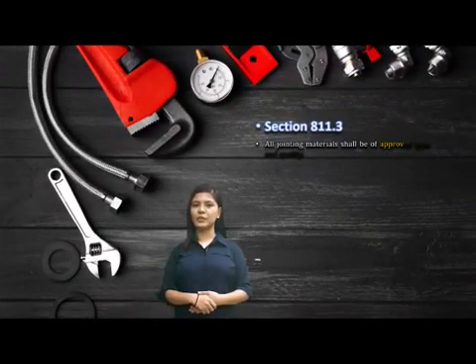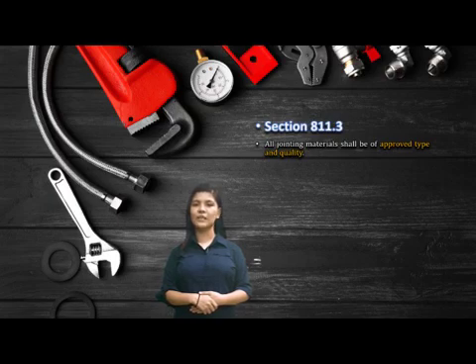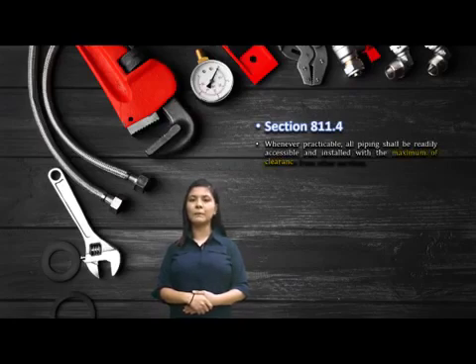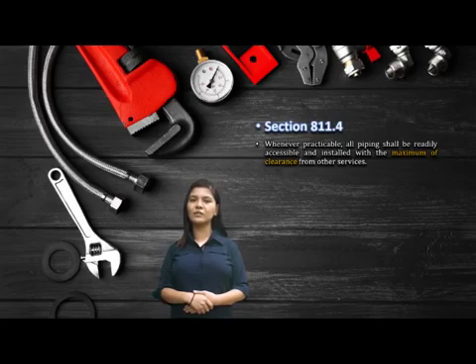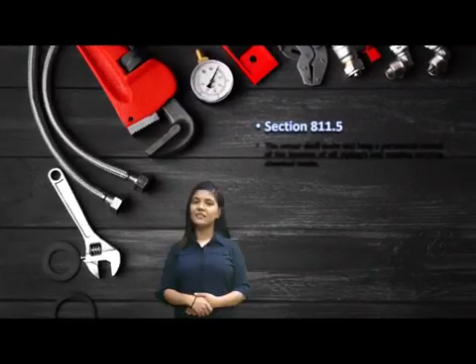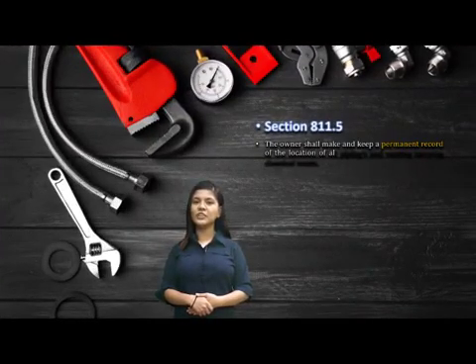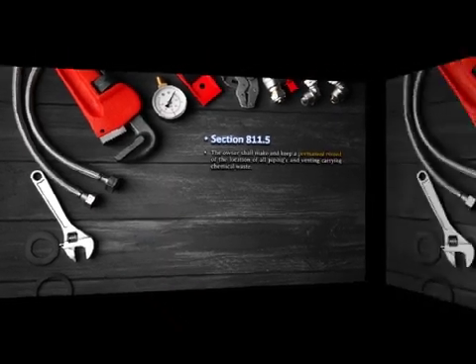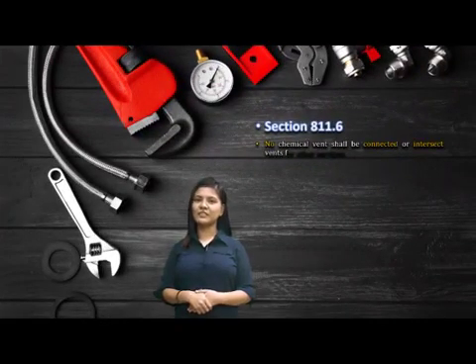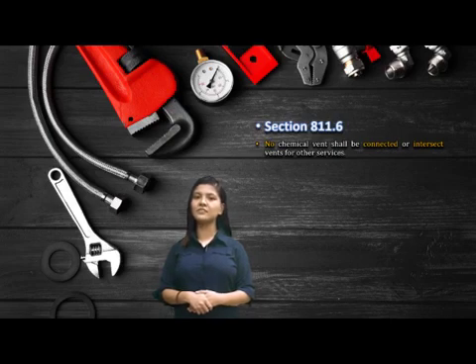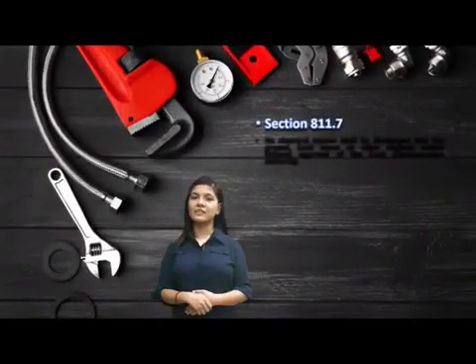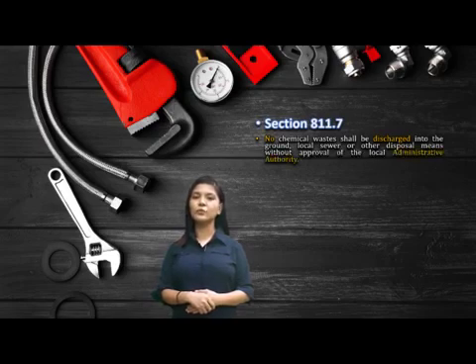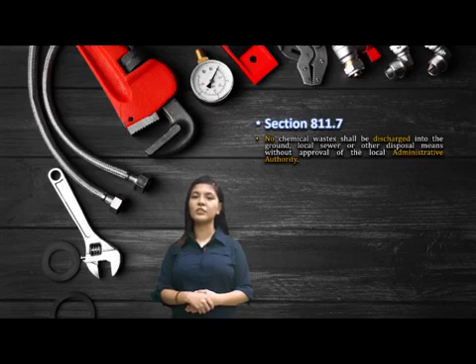Section 811.3: All joining materials shall be of approved type and quality. Section 811.4: Whenever practicable, all pipings shall be readily accessible and installed with a maximum of clearance from other piping. Section 811.5: The owner shall make and keep a permanent record of the location of all pipings and venting carrying chemical waste. Section 811.6: No chemical vent shall be connected to or intersect any other vent or piping. Section 811.7: No chemical waste shall be discharged into the ground, local sewer, or other disposal means without approval of the local Administrative Authority.